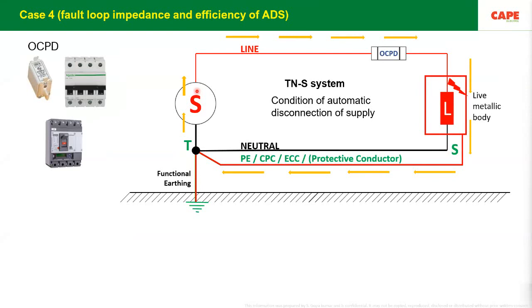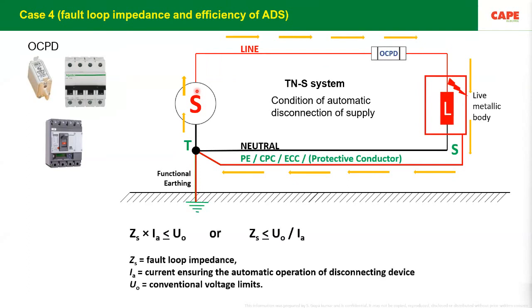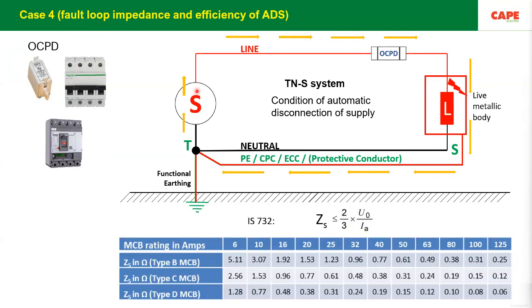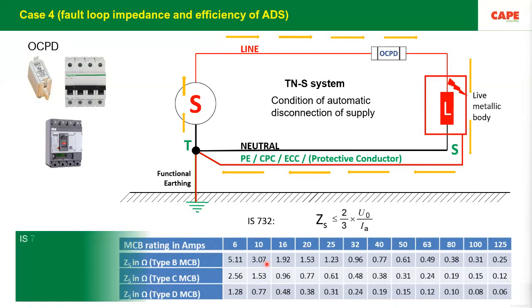If you have more and more fault current, the protective device will be efficient and the disconnection time will be lesser and lesser. So one of the fourth important points is to ensure that the fault loop impedance is lesser than the allowed limit and the device is able to trip. In the upcoming National Electrical Code, we have included this table which says every MCB, you can see MCBs are of type B, type C, type D, depending upon the type of the MCB and its rating. The maximum allowed fault loop impedances are included in a table.